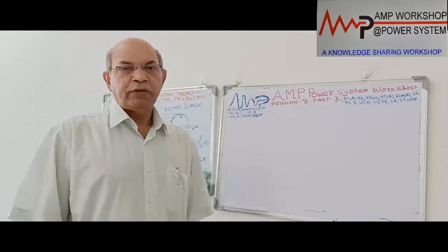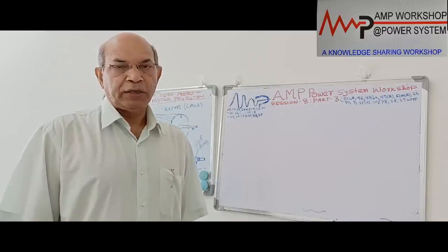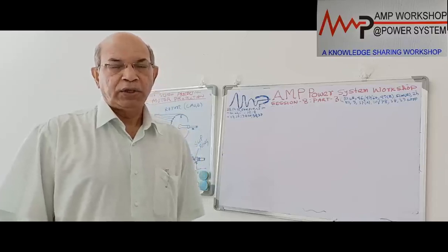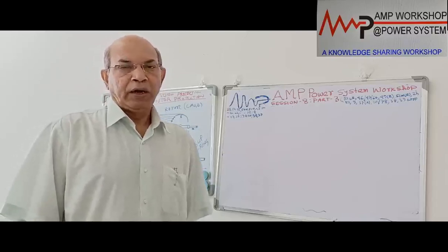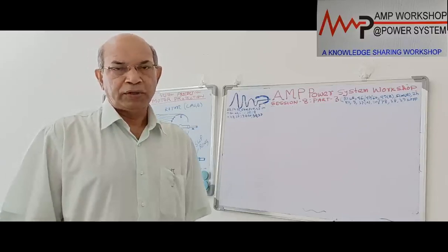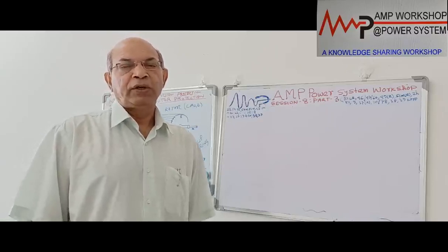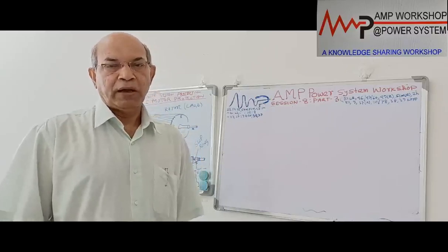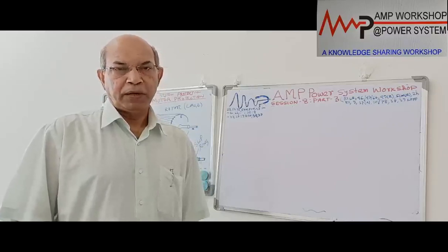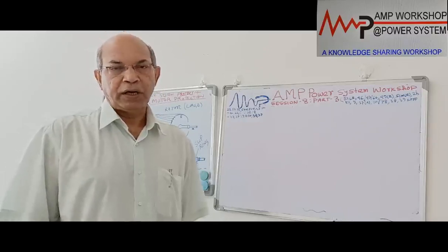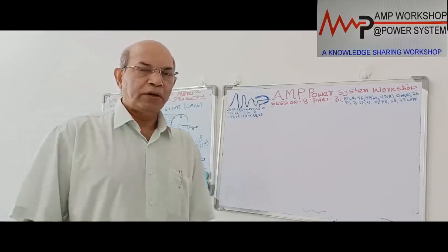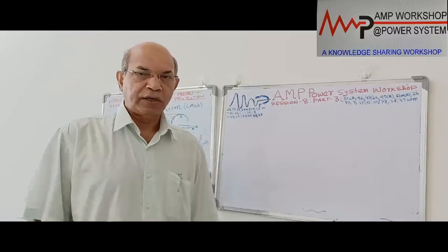In the locked rotor protection, we said that during a jam condition, or if the rotor is locked due to a high inertia load, or if during running condition there is single phasing or a huge under voltage, the motor will not be able to deliver adequate torque. Even though one of the phases is open circuited, the other two phases will carry about 86% of the locked rotor current, still the motor may not be able to produce the required torque and the motor can come to a standstill.